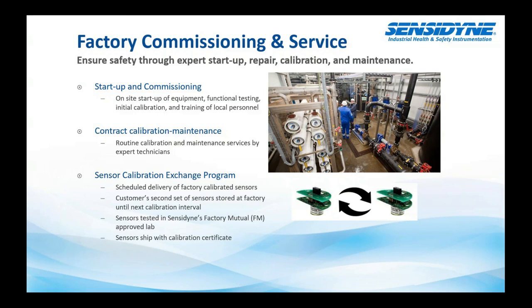Some customers are storing them in their shop. They're exposed to the target gases, to moisture, to heat. All those things will degrade your sensor over time and will shorten its life. So it's important to store these in a dry, cool area. And that's what we do for you at the factory, as well as the calibration. So it takes a lot of the guesswork out of your calibration program, puts it all on us to remind you that it's due. And then, like I said, you can access all that calibration data on the ASI and the SenseAlarm Plus right from the transmitter. And we also give you a calibration certificate that comes with it.